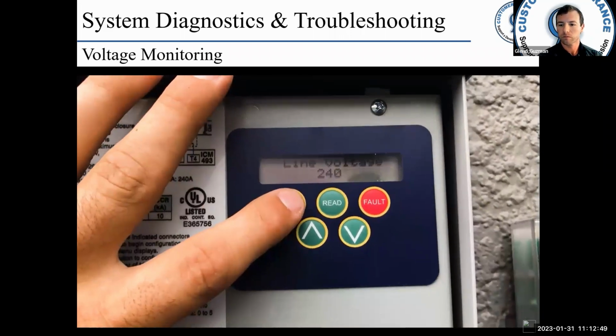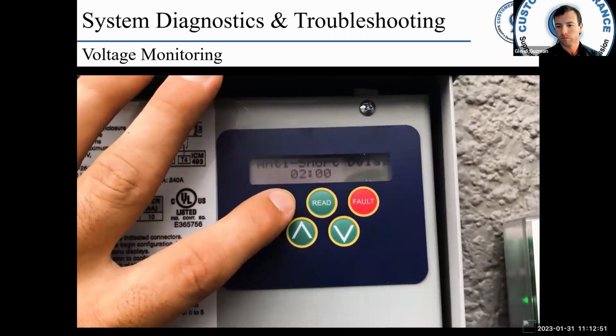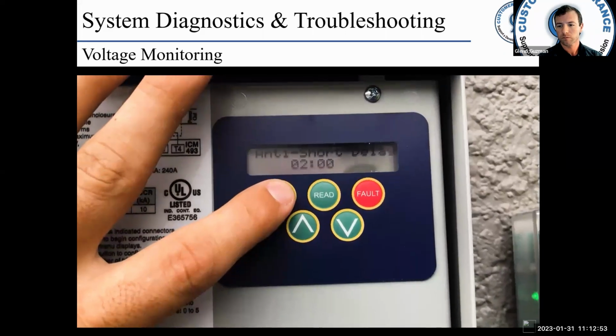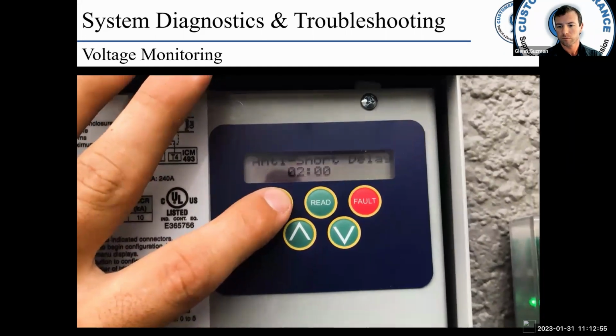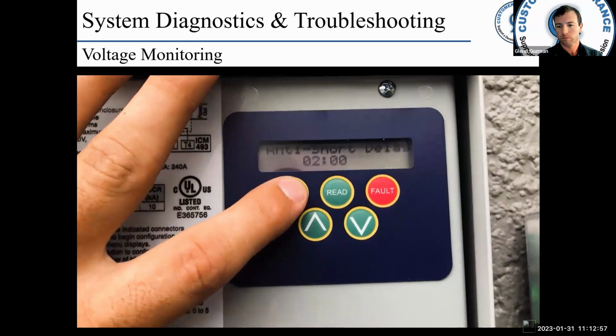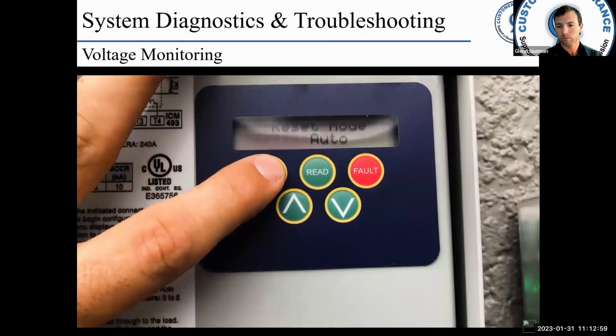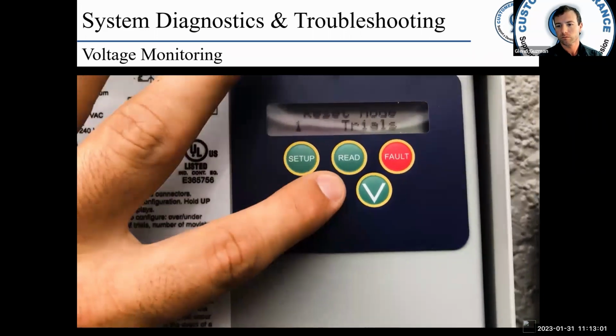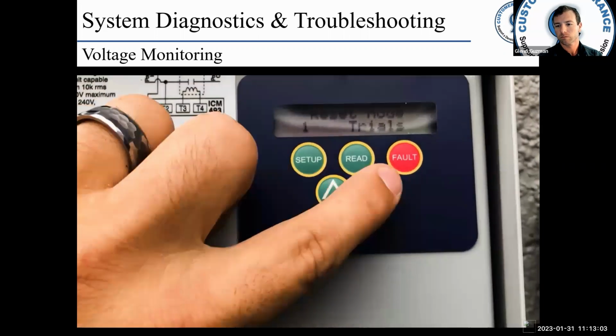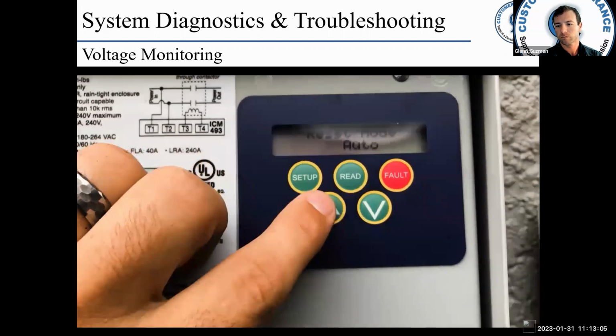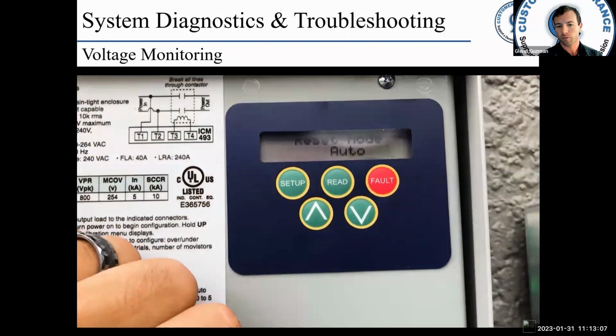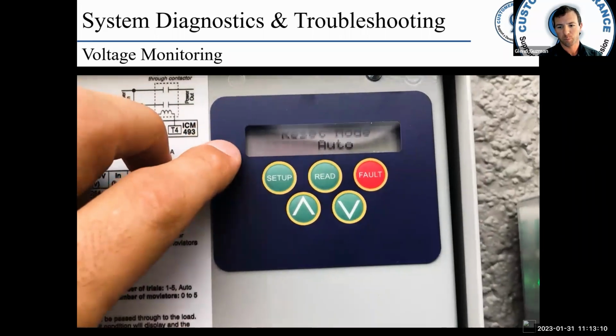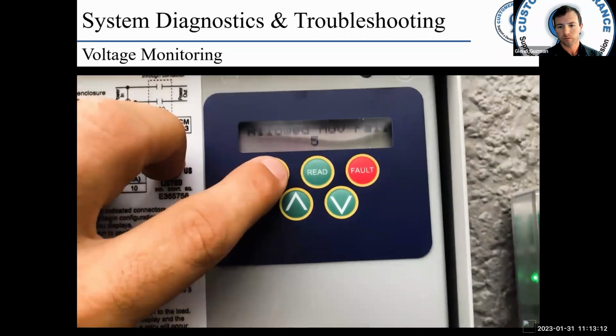Then we're going to have line voltage 240 over under, anti-short cycle delay. This comes at 30 seconds. I bumped it up to 2 minutes. Reset mode, so you can change this from one trial or automatic. I went over the pros and cons with the customer and we chose to go with automatic on this one.